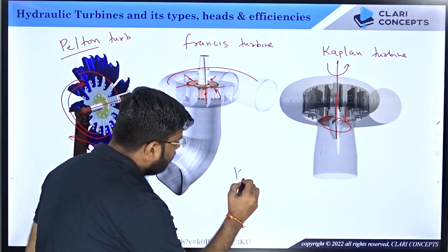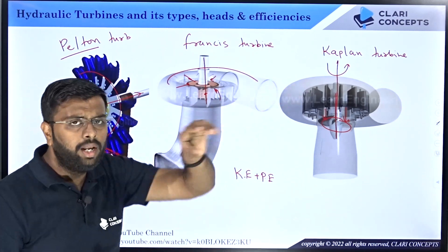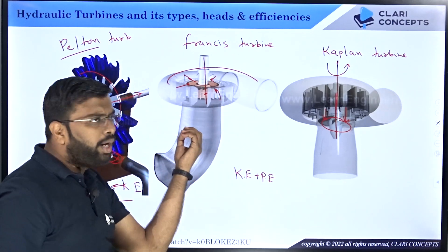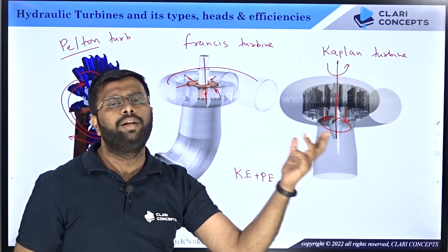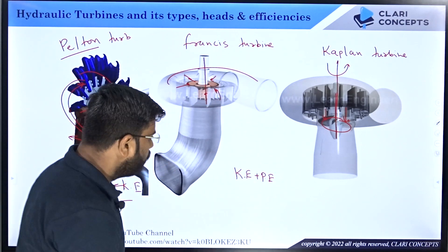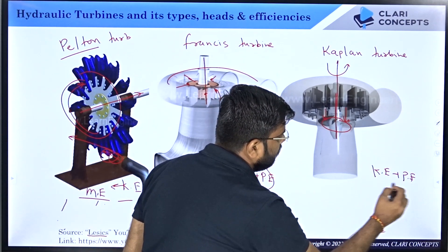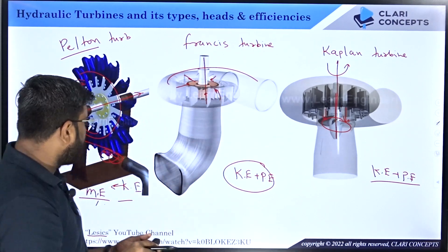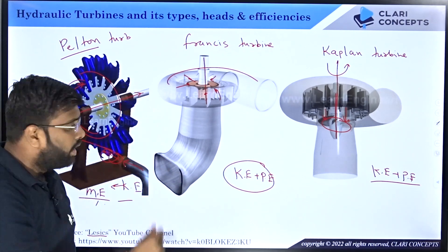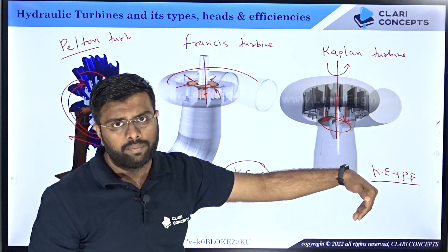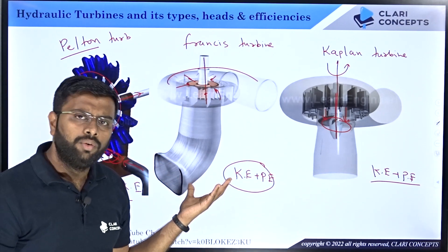The Francis turbine uses both kinetic energy plus pressure energy. When water comes to the inlet, both pressure and kinetic energy are present, and the turbine extracts both to drive the generator. Similarly, Kaplan also uses both kinetic energy plus pressure energy. For Pelton, flow rate is relatively small but head is high. For Kaplan, flow rate is high but head is low — so for low head dams you use Kaplan. Francis is used for medium head and medium flow rate operations.